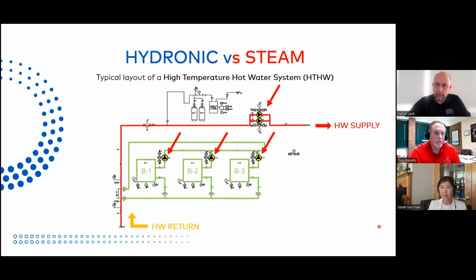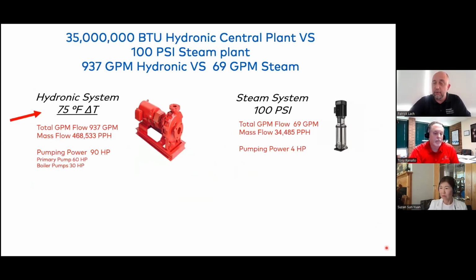Let's move on, Tony. So with a 75 Fahrenheit rise, not 40, not 20, with a 75 Fahrenheit rise, hot water, you will need 937 GPM of water, which means 468,000 pounds per hour of mass flow, mass energy, for a total pumping of 90 horsepower. The same steam system to generate 35 million BTU, in a closed loop system, you will need only 69 GPM, 35,000 pounds per hour of mass flow energy. This is huge. Huge difference in electric grid relief. Also, these are tremendous numbers. Next slide.